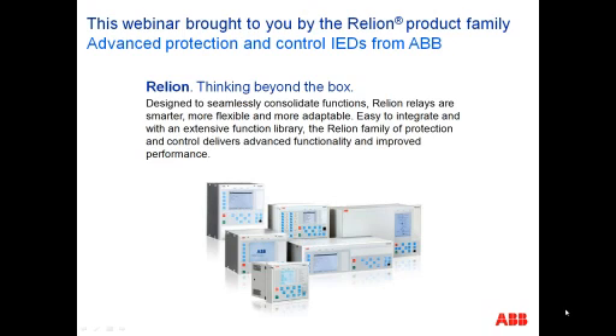POTT is permissive overreach, and PUTT is permissive underreach. And permissive underreach is where you would use an underreaching zone, in particular zone 1. If you have a zone 1 operation, you send a permission to the remote end to trip. And normally, if you have a zone 1 operation, that would be the case. And at the remote end, you would have to receive permission, but you trip on an overreaching setting. It's underreach to send the permission, but it still will trip with permission and the operation of an overreaching zone.